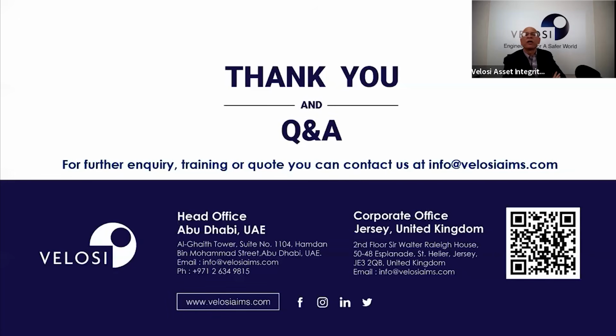What is the classification for transformer installation? Practically, transformers are installed in the substation. In the substation, as such, they are non-classified, but there is oil inside the transformer and switchgear, and similarly you have a UPS system inside the substation. So we need to have proper ventilation in those areas. Accordingly, hazard area classification is applied to maintain proper ventilation, so that hydrocarbon fluid does not accumulate inside the substation if there is any leakage from the transformer or switchgear. Similarly, you know that hydrogen is produced by the UPS batteries, and proper ventilation is also required there, so that it does not make an explosive mixture inside the battery room.